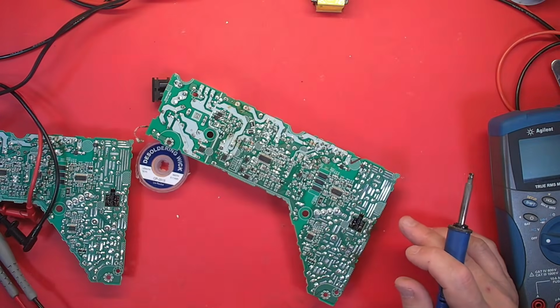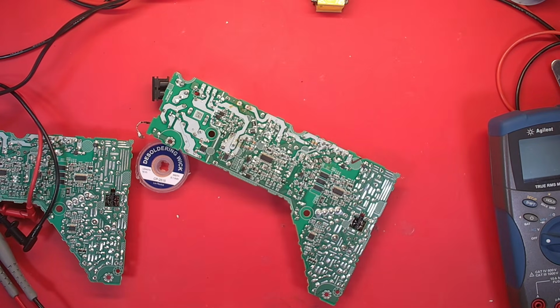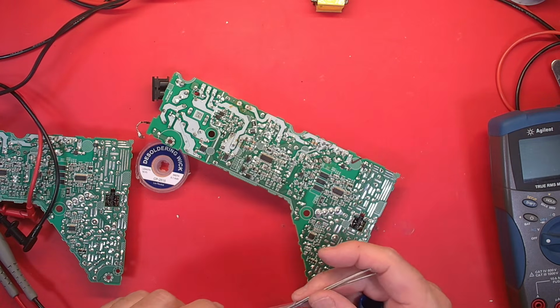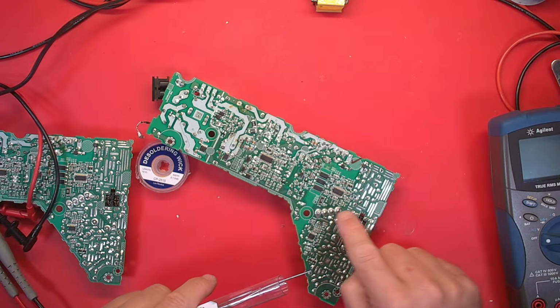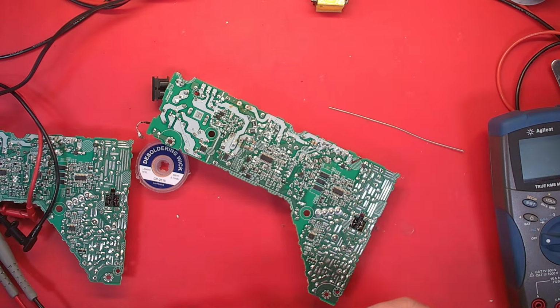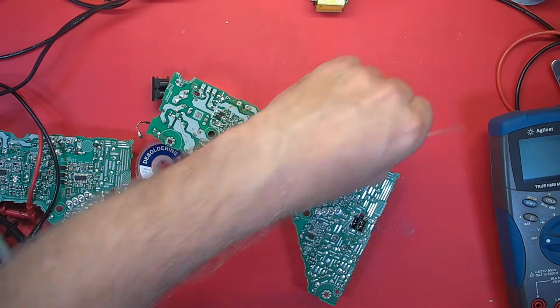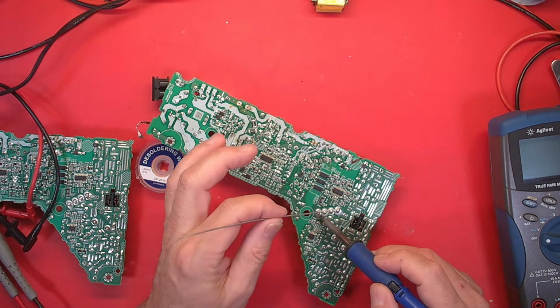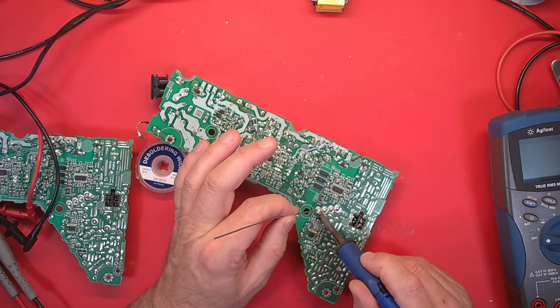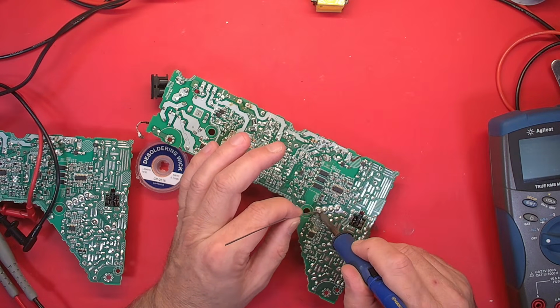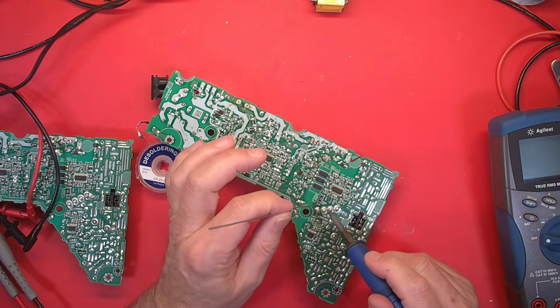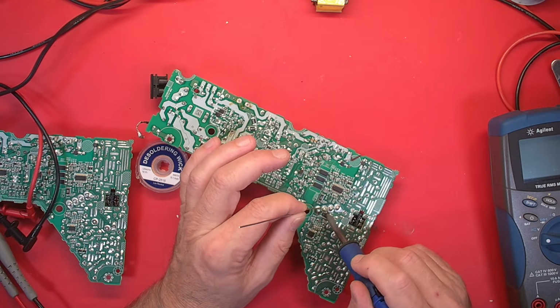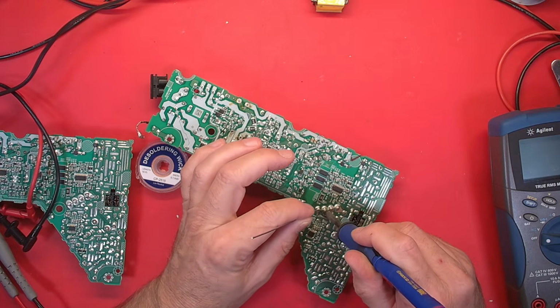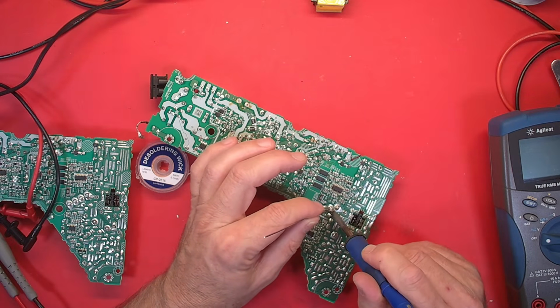Now this, I always use a little bit of low melt, because wicking those big old contacts clean... because these contacts on this side are actually just twisted wire coming out of that coil, out of that transformer. It's not like a solid piece of leg of copper, it's braided, twisted copper. I don't know how many strands it has, but it's stranded copper wire. That's what I was trying to say.